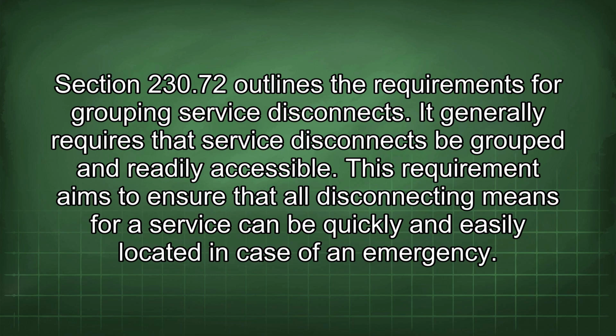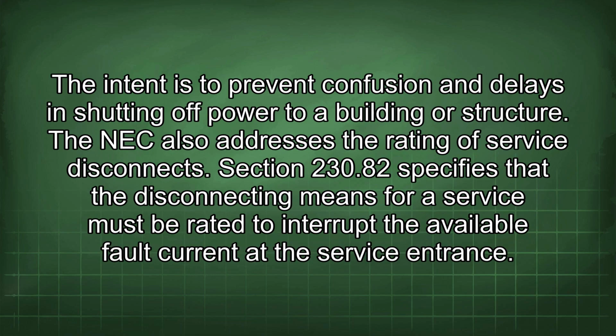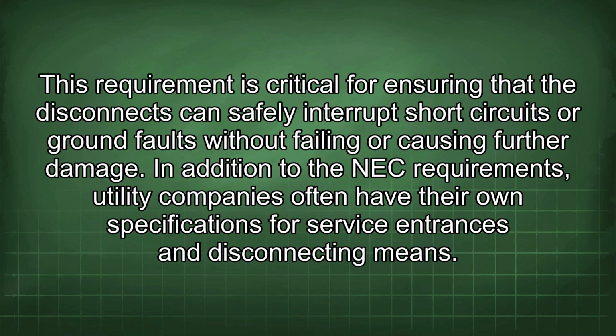This requirement aims to ensure that all disconnecting means for a service can be quickly and easily located in case of an emergency. The intent is to prevent confusion and delays in shutting off power to a building or structure. The NEC also addresses the rating of service disconnects. Section 230.82 specifies that the disconnecting means for a service must be rated to interrupt the available fault current at the service entrance. This requirement is critical for ensuring that the disconnects can safely interrupt short circuits or ground faults without failing or causing further damage.